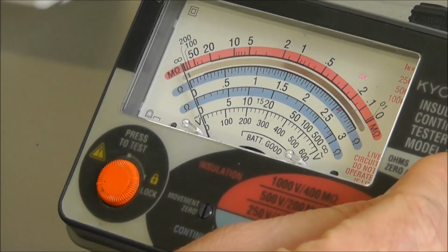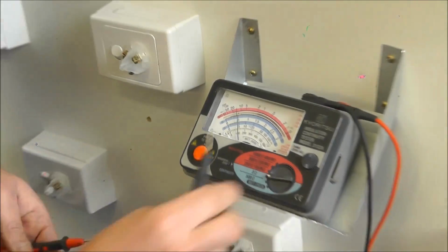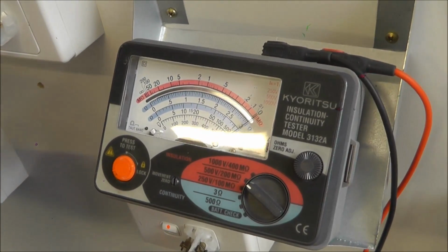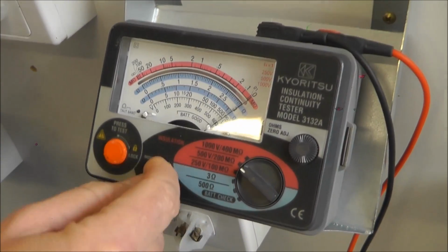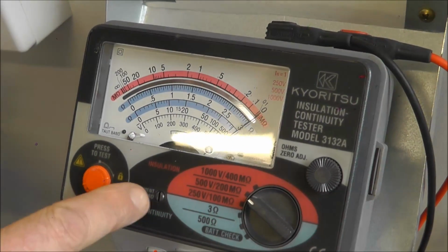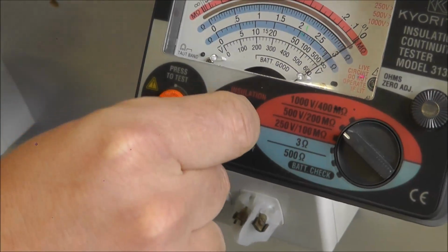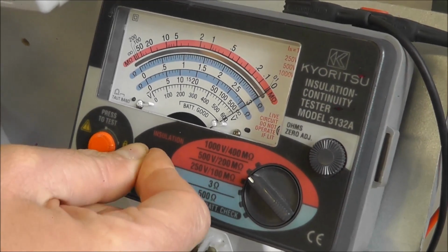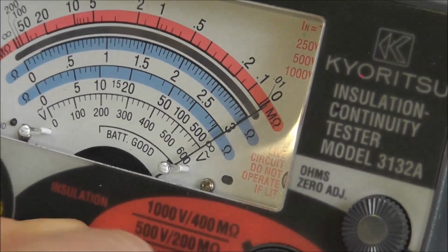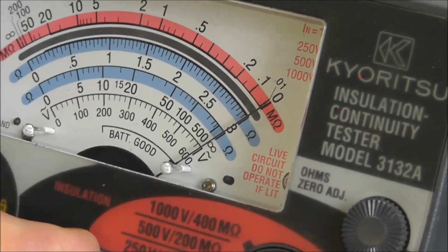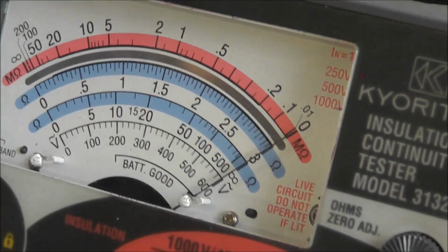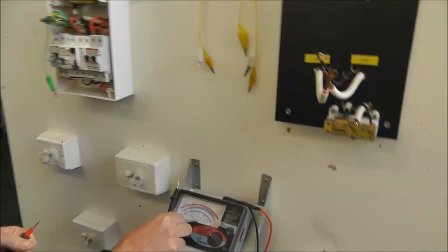If you don't know about the second part of your megger, on 500 volts, when you go together like so, see how I'm a bit below 0 there, Dobbo? This adjuster here is like your zero adjust, to get 0 mega ohms on 0 mega ohms. A screwdriver would be a bit more handy than my fingernails. Oh, see that there, Dobbo? See that move there? See now 0 mega ohms on 0 mega ohms. Right, it's very important.